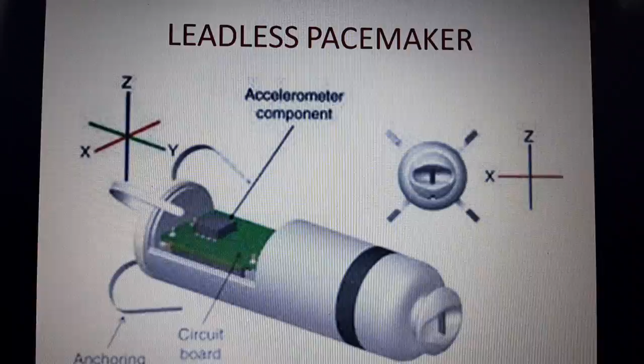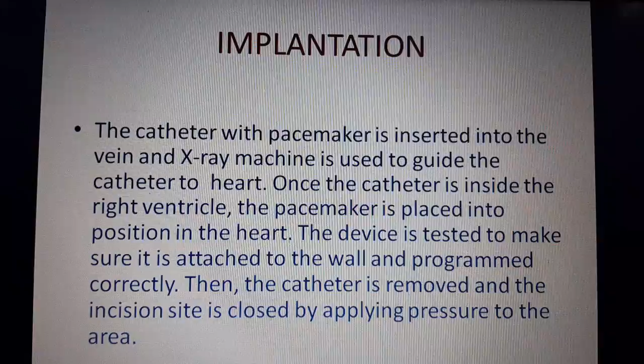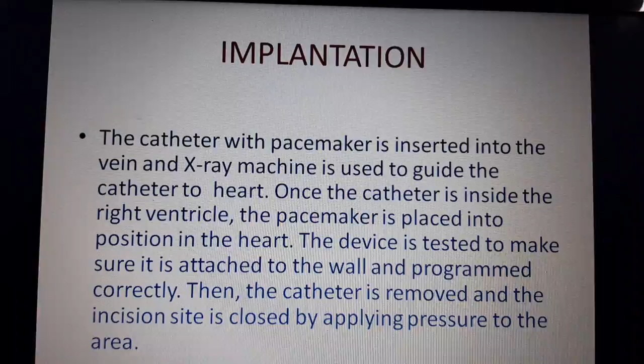Then the implantation of the device: the catheter, that is a long tube with the pacemaker, is inserted into the vein, and the X-ray machine is used to guide it to the heart. Once the catheter is inside the right ventricle, the pacemaker is placed into the correct position in the heart, and the device is then tested so as to make sure that it is attached to the wall of the heart and is programmed correctly. Then the catheter is removed and the incision site is closed by applying pressure to that area.